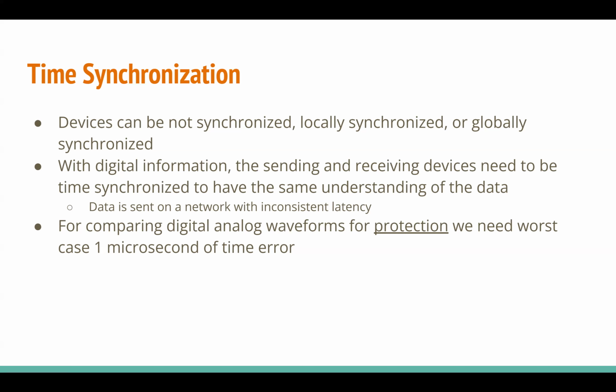So when we're worried about comparing analog waveforms in terms of protection, the worst case difference in time that the 2 relays can have is 1 microsecond. So hopefully that's blowing your mind a little bit, that's a very small amount of inaccuracy that would cause problems. So basically, if relay A thinks it's 1 microsecond later than what relay B thinks, we can't use those for protection in a digital system. So we have to have these devices synchronized to better than 1 microsecond of error.